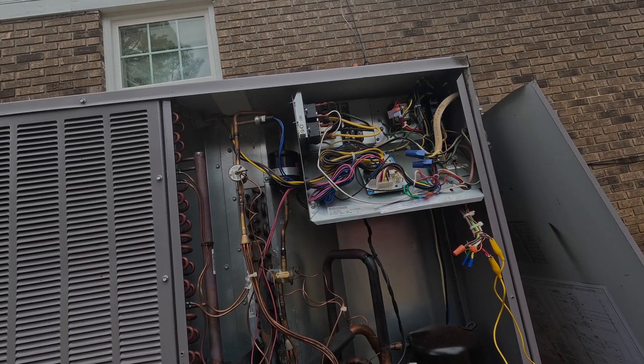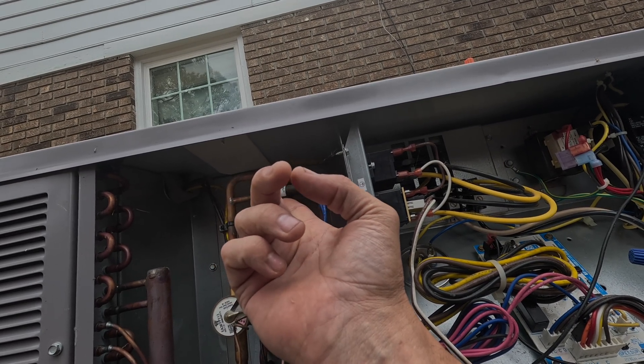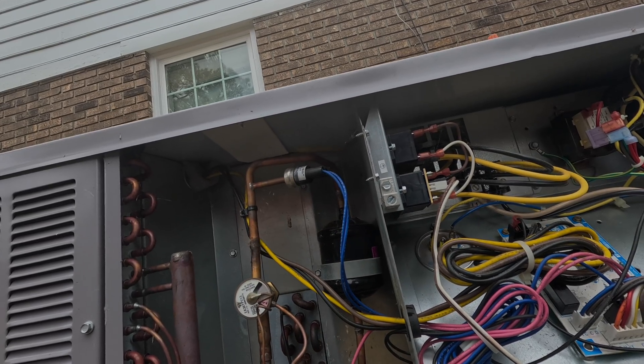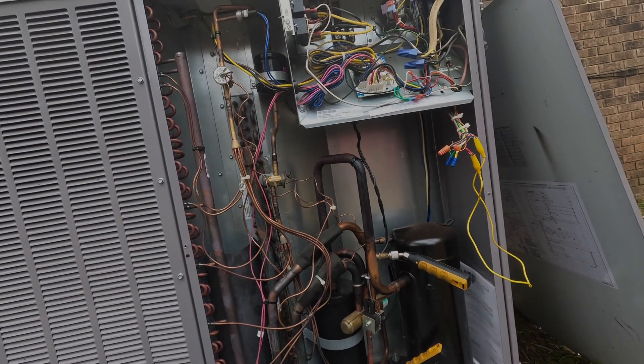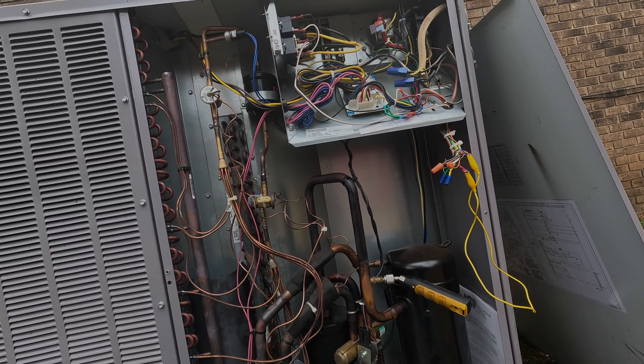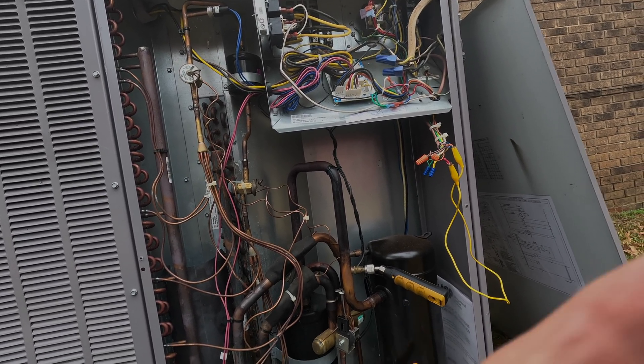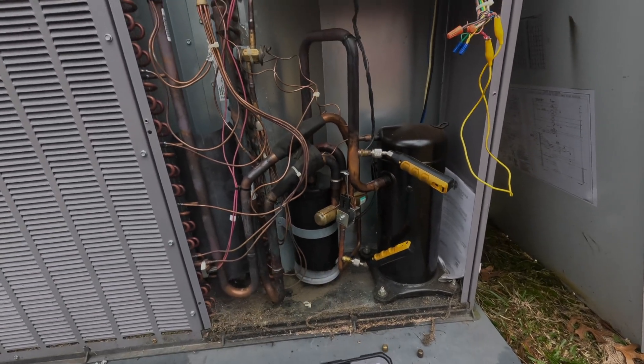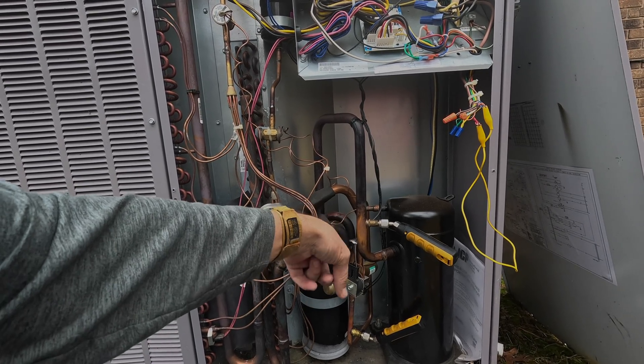I think it's the TXV right here, and what's cluing me in is this loss of charge switch. This side still has pressure, but there's no pressure on this side right here. I don't know if y'all saw the accumulator icing up — it was iced up to here. That means there's low pressure on the suction.